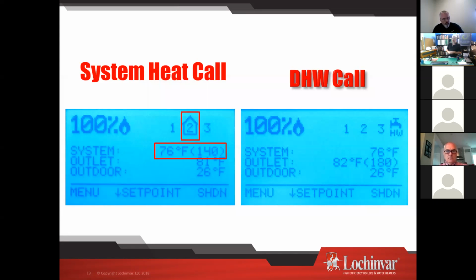Now down below, where I've highlighted with the red box, any number that's in parentheses is a target temperature. So right now in this case, the system is at 76 degrees. The boiler is targeting 140 degrees. We have 81 degrees coming out of the boiler, okay? If we jump over here to domestic hot water call, 2 things have happened. 1, I now have the hot water spigot, clue for I've got a domestic hot water call.